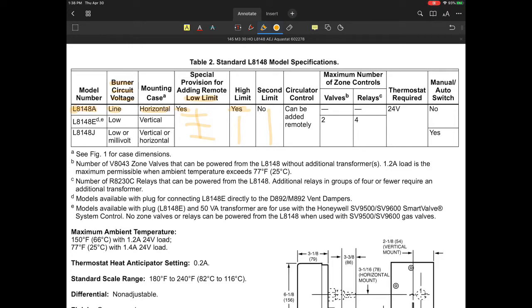So in your bigger commercial jobs, you likely would have a different type of limit, where you would have another device mounted in a different well, and that could act as the secondary limit. I would say that's extremely common in commercial jobs, where we would have an Aquastat high limit on a typical boiler, and then the secondary limit could potentially even be what we call an operating control, where we could actually control the boiler at varying temps. That's another way to deal with this.